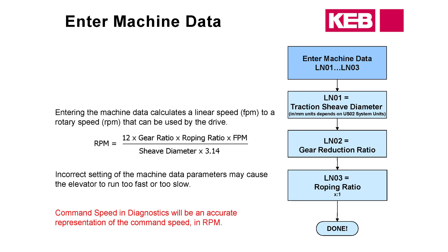You've done the encoder learn and the motor learn, and now you want to enter in the machine data. This is where you enter the sheave diameter and gear reduction ratio if you have a geared machine. If you're using serial speed control, the controller writes a direct RPM value to the drive, so the machine data isn't going to affect the speed of the car. However, if you're using digital or binary speed control where the drive is in charge of the profile, changing your sheave diameter or gear reduction ratio is going to change your speed.